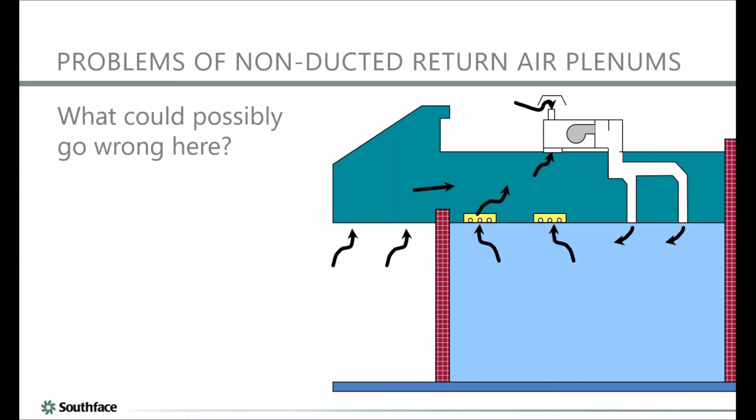And that's a real problem. And this is a great pathway for tons of humidity to get in, to really be sucked in. Well, and also, if this was a school or some sort of drop-off for children, you've got idling cars, or school buses. Or stinkier. So you're pulling in all this polluted outside air.